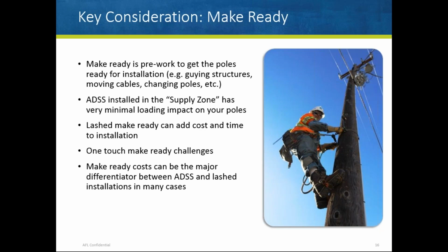ADSS installed in the supply zone minimizes guying of structures and, in most cases, the need to move cables or worry about clearance concerns, since the ADSS is higher up on the pole. Lashed installations, especially in the communication zone, can add significant time and cost to make ready, and this can be a major differentiator between ADSS and lashed.